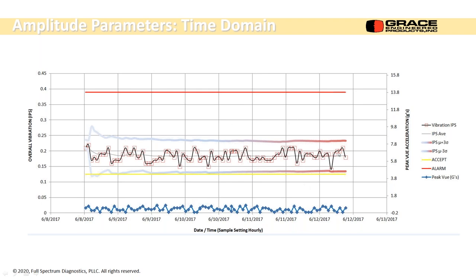And it's constantly updating because you're constantly grabbing data. This was once every hour for 4 days, and I can see a change in my alarm levels, which is pretty impressive. There's another parameter down here. This is velocity for my main trend that I'm looking at. This is high frequency acceleration, and it's a filtered measurement that we'll get into shortly. This one's called PeakVue, but it's a high frequency energy.